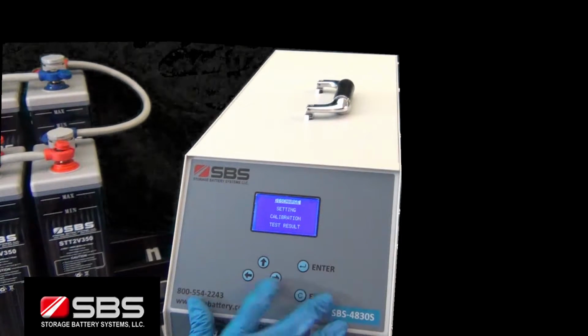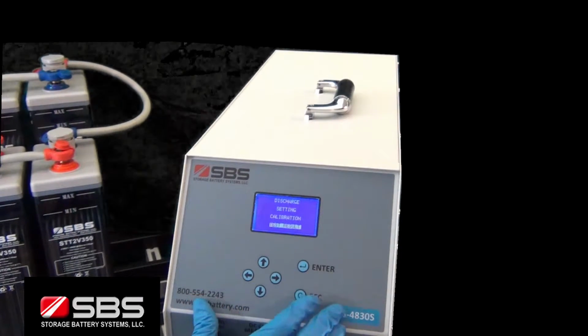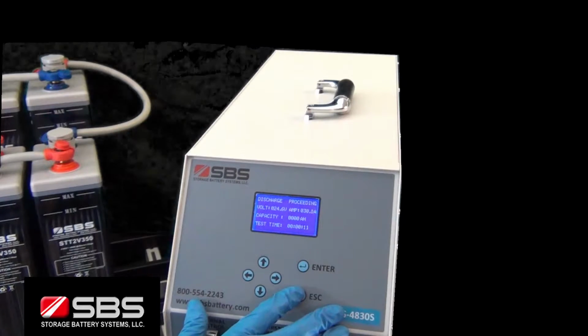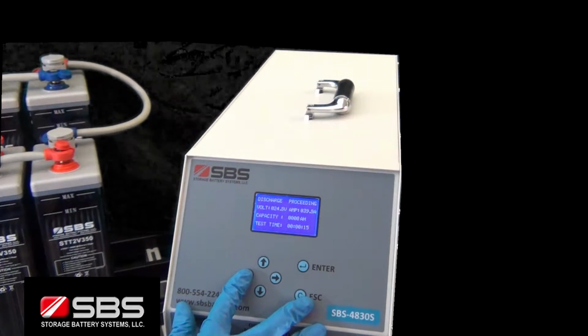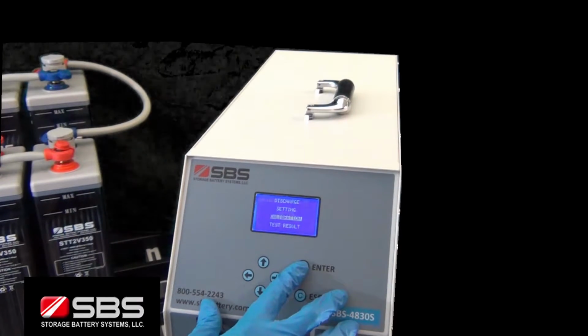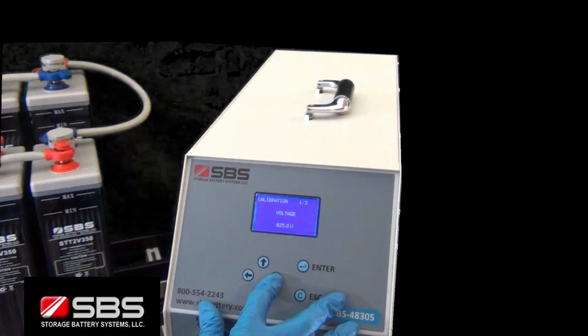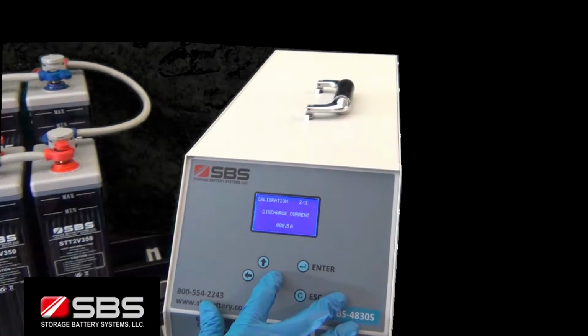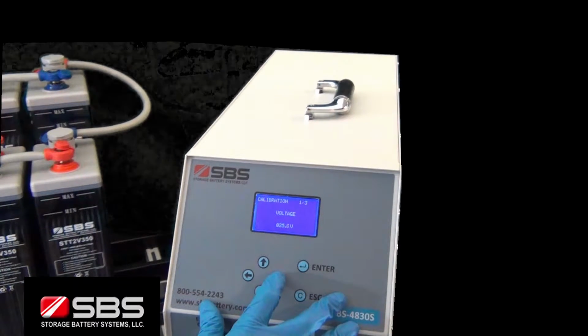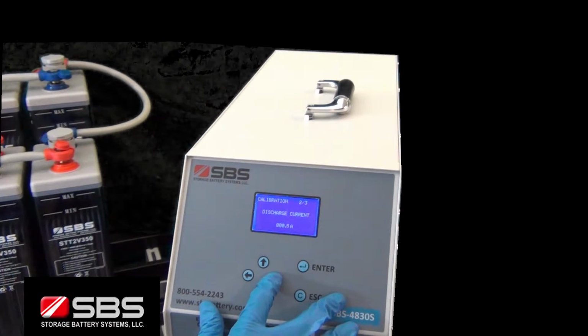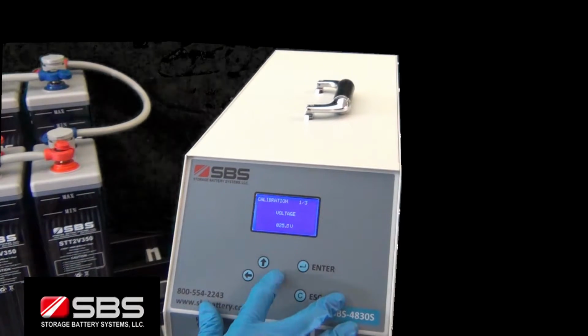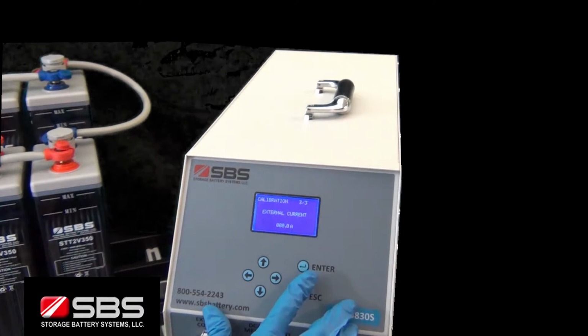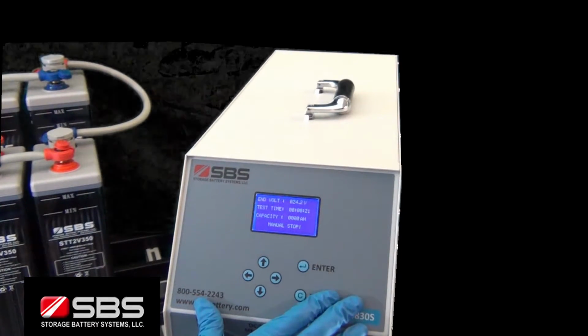Now, let's run through some of the on-screen menus. Selecting Discharge in the main menu will be used to begin the load bank test. The SBS S-Series supports user calibration through the calibration option. Here we can calibrate the display voltage, discharge current, and the external current from the current clamp. Selecting the Test Results feature will display the recorded results of the past load bank test data.